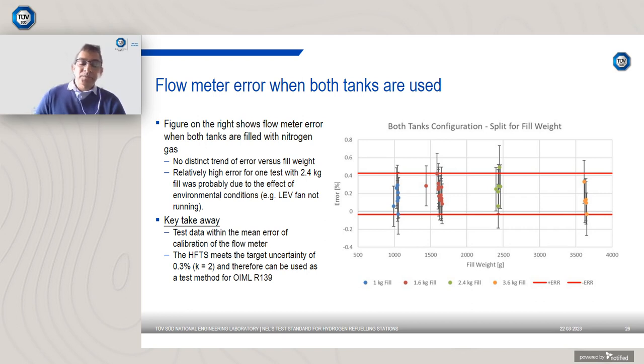The relatively high error, of course, that you can also see is, for example, for the 2.4 kilogram fill, and this is possibly due to an environmental condition effect, because what we found there was that the LEV fan in the James Young building wasn't operating at that particular moment for that test, and the fan would randomly rotate. You could see the effect of this on the ring scale, where there were fluctuations. So essentially it showed that you need to have quite a stable environment if you want to have our target uncertainty.